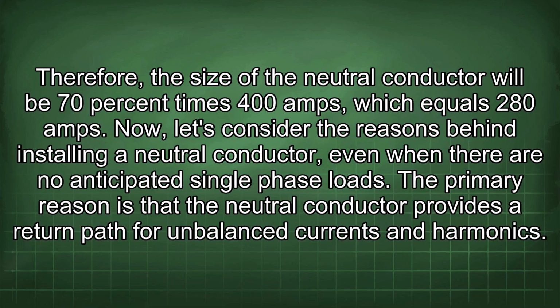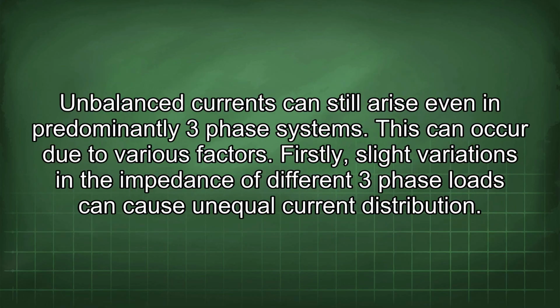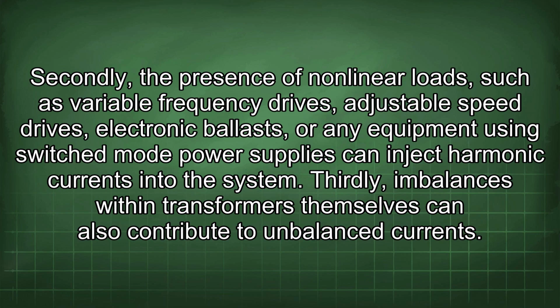Now, let's consider the reasons behind installing a neutral conductor, even when there are no anticipated single-phase loads. The primary reason is that the neutral conductor provides a return path for unbalanced currents and harmonics. Unbalanced currents can still arise even in predominantly 3-phase systems. This can occur due to various factors. Firstly, slight variations in the impedance of different 3-phase loads can cause unequal current distribution. Secondly, the presence of nonlinear loads, such as variable frequency drives, adjustable speed drives, electronic ballasts, or any equipment using switched-mode power supplies can inject harmonic currents into the system. Thirdly, imbalances within transformers themselves can also contribute to imbalanced currents.